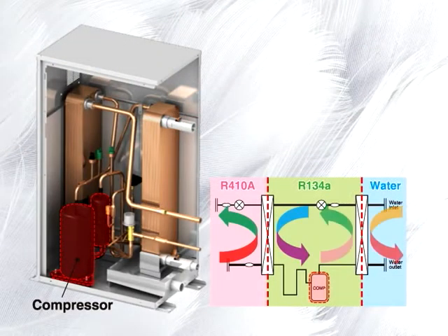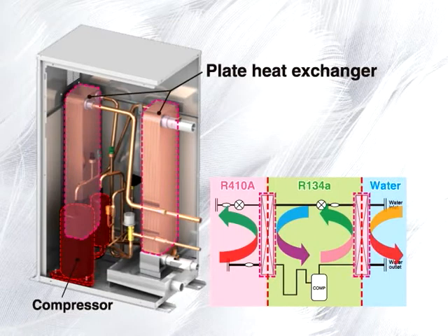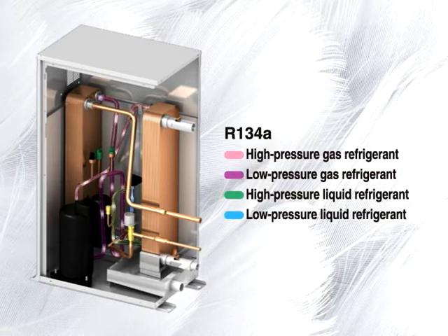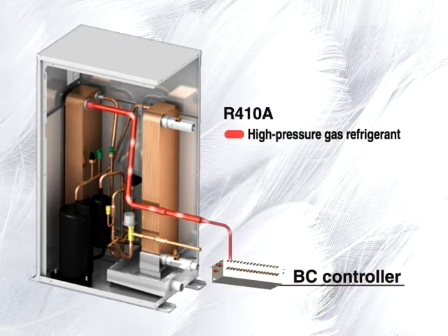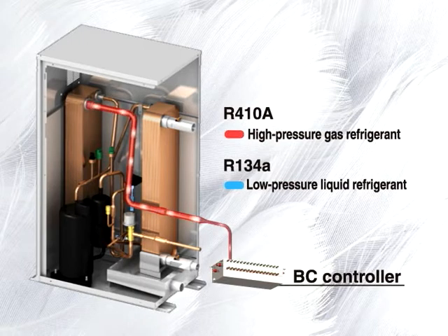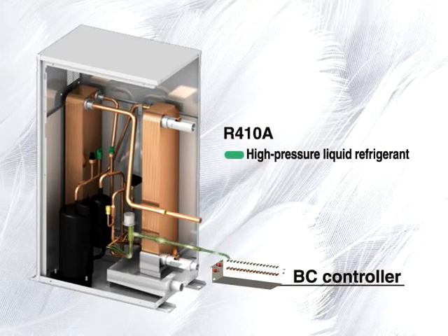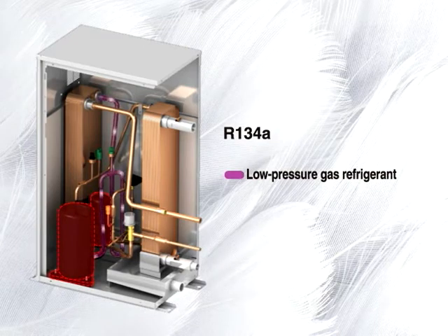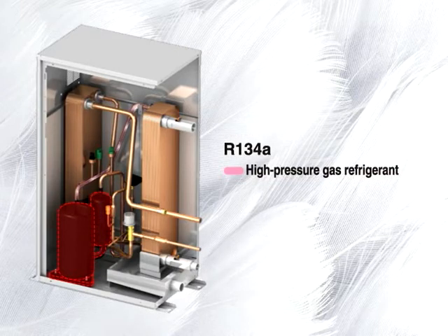The booster unit is equipped with a compressor and a 2-plate heat exchanger, in which the R134A refrigerant circulates. High-pressure R410A gas refrigerant is delivered from the BC controller. The R410A refrigerant heat exchanges with the low-pressure R134A liquid refrigerant circulating through the first heat exchanger and circulates back to the BC controller as high-pressure liquid refrigerant. To raise the temperature, low-pressure R134A gas refrigerant is compressed by the compressor to become high-pressure gas refrigerant. Compared to the R410A refrigerant, R134A refrigerant requires less pressure to raise the temperature.